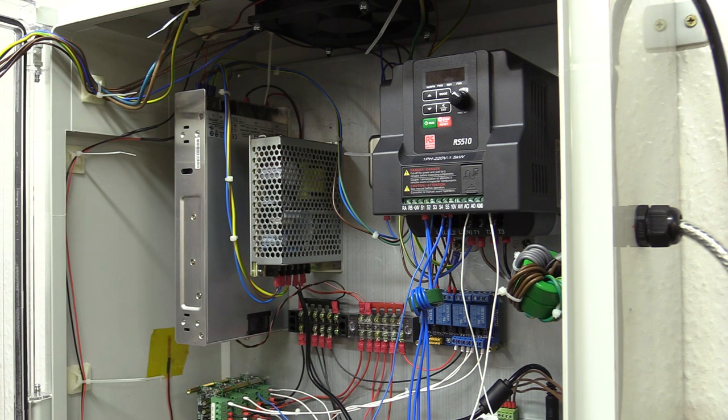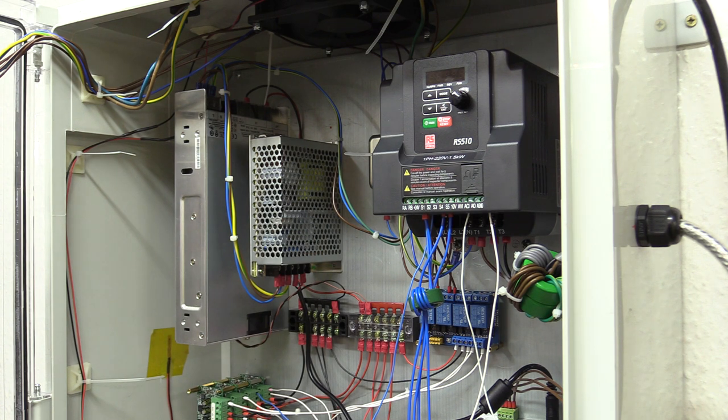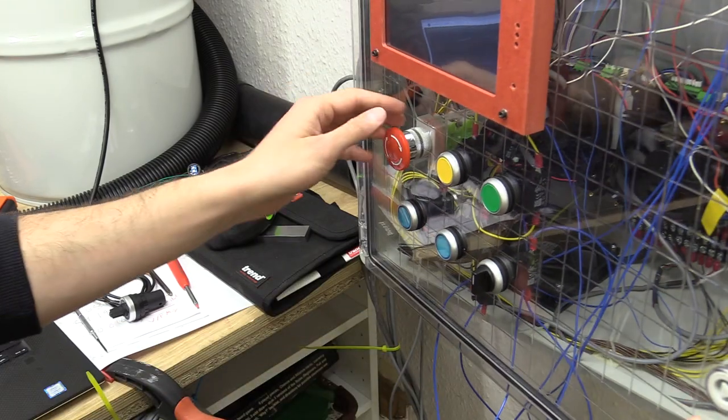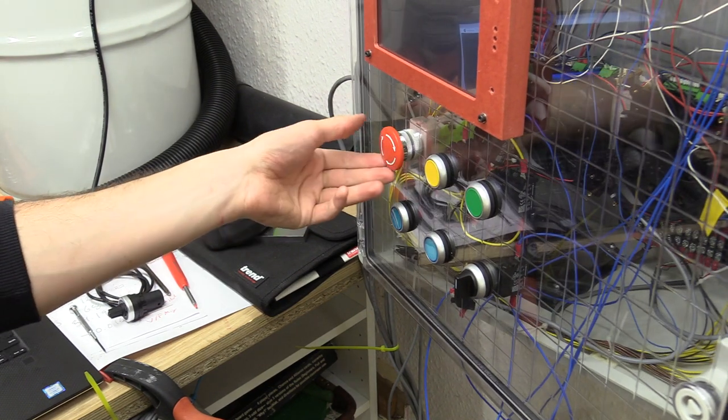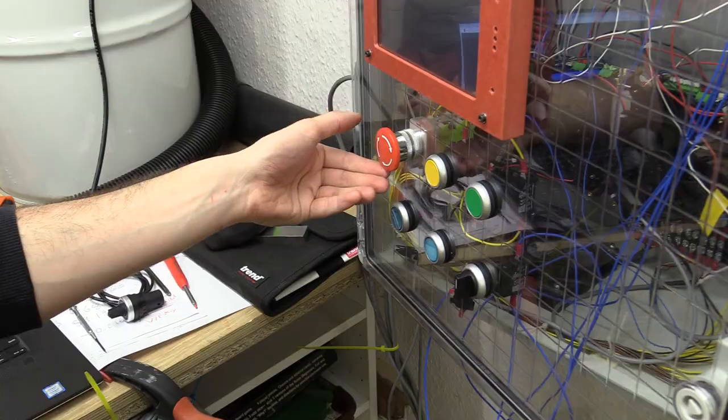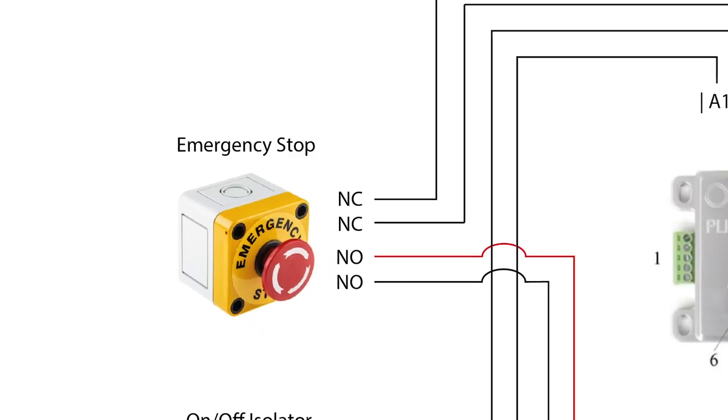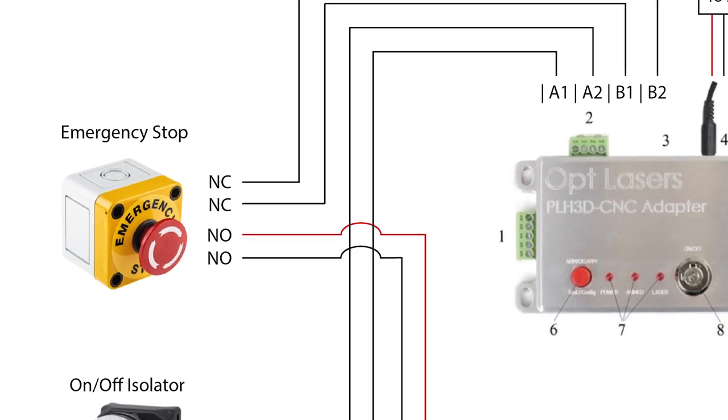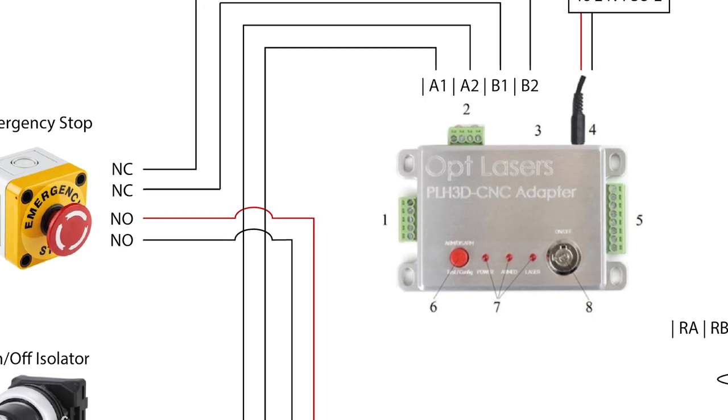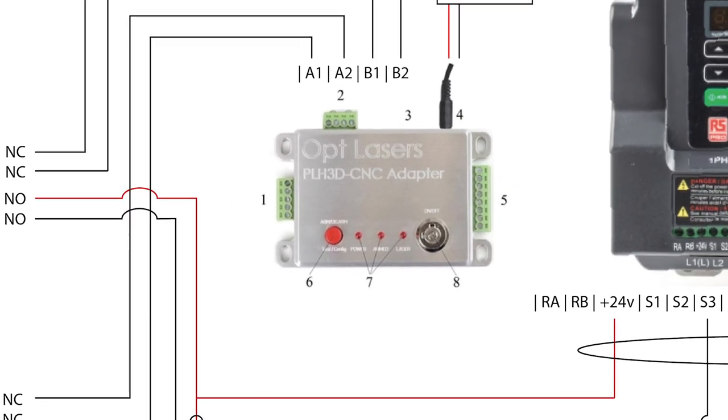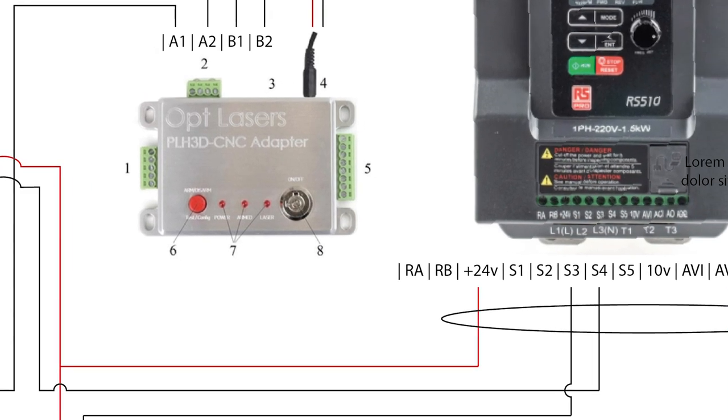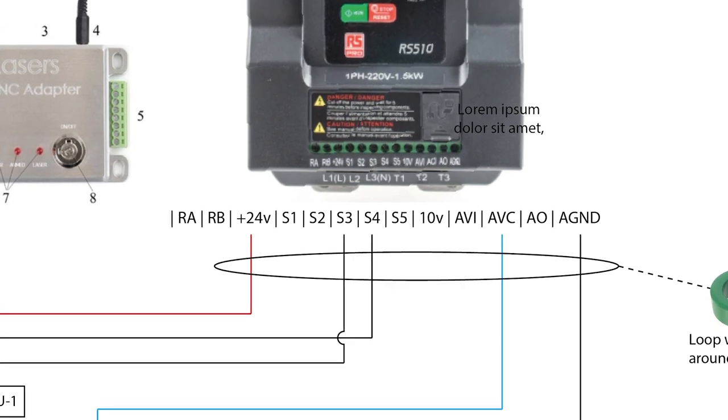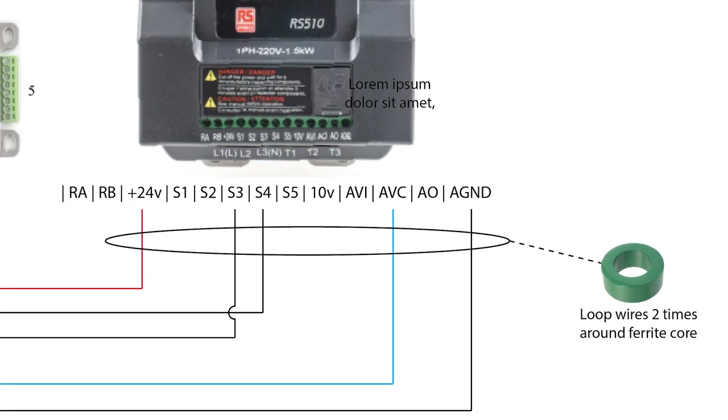I've also wired in an e-stop directly to the VFD so that it will stop a little bit quicker if the e-stop is pressed. But what I've found is I need to use a latching style emergency stop, so like this one here. So when it's pressed it clicks into place and then you have to twist to reset. The S4 input is connected to the emergency stop, which is now a latching type and performs option 14 rapid stop deceleration to stop. The speed of which is defined by option 00-17 and is set to 5 seconds. Under normal M5 stopping operation, option 00-15 sets the speed and is around 9 seconds. Input S5 is unused.